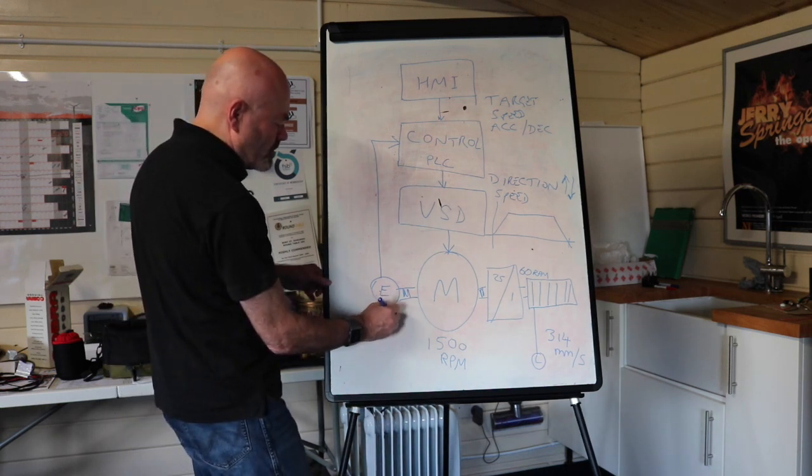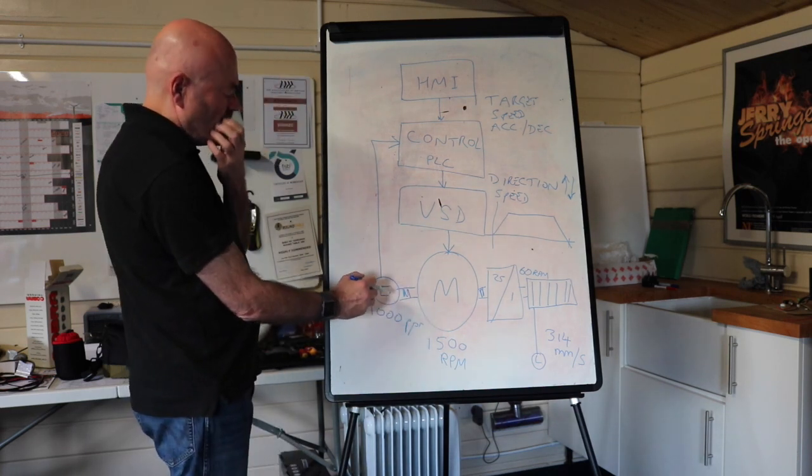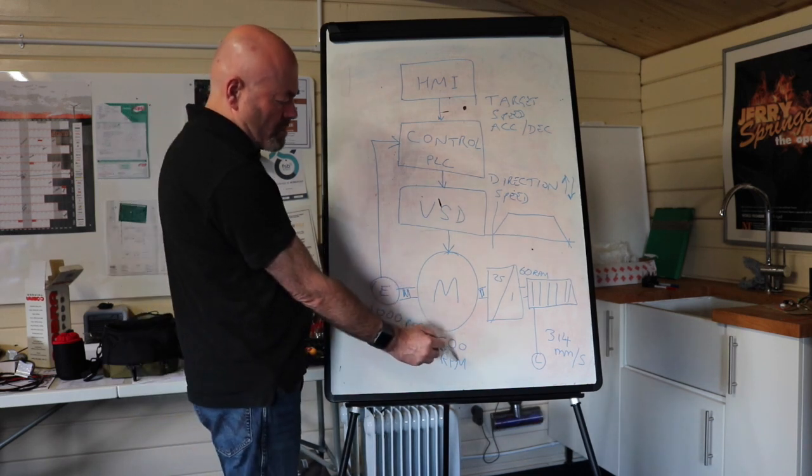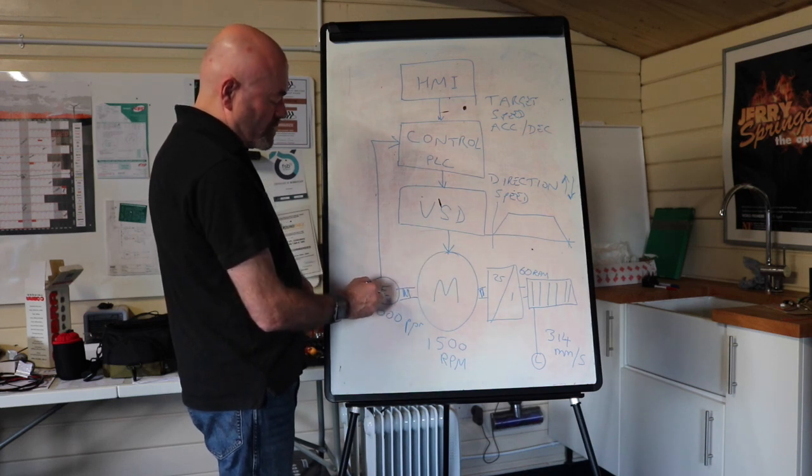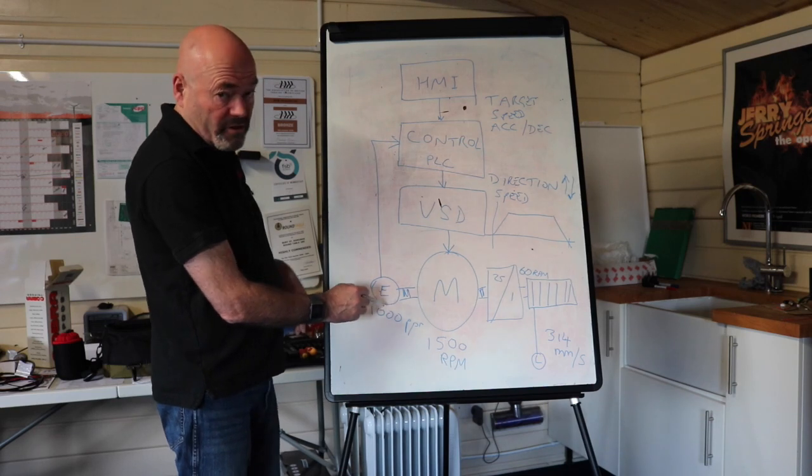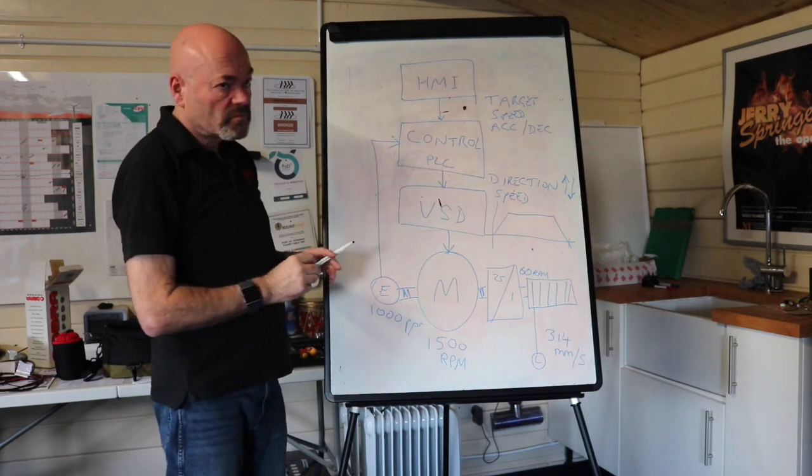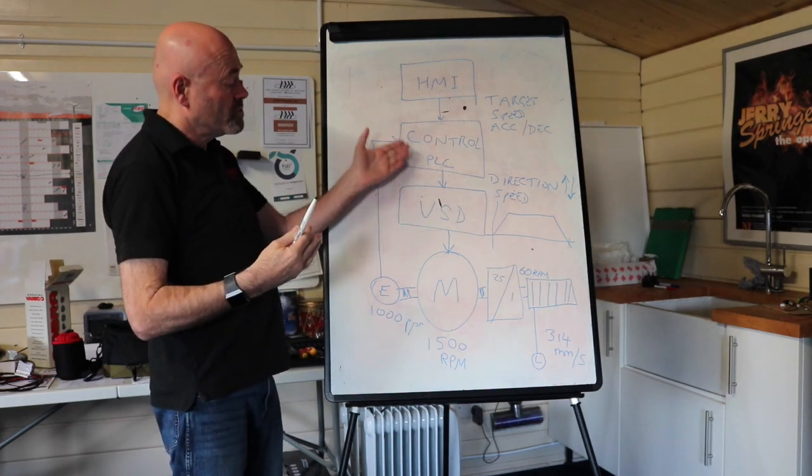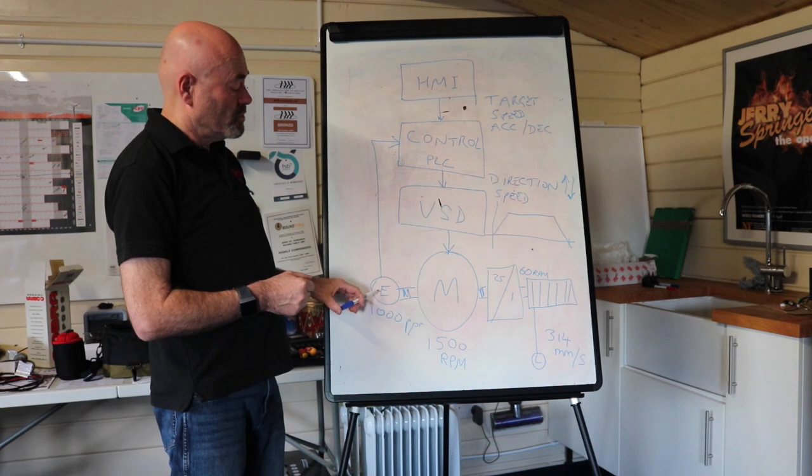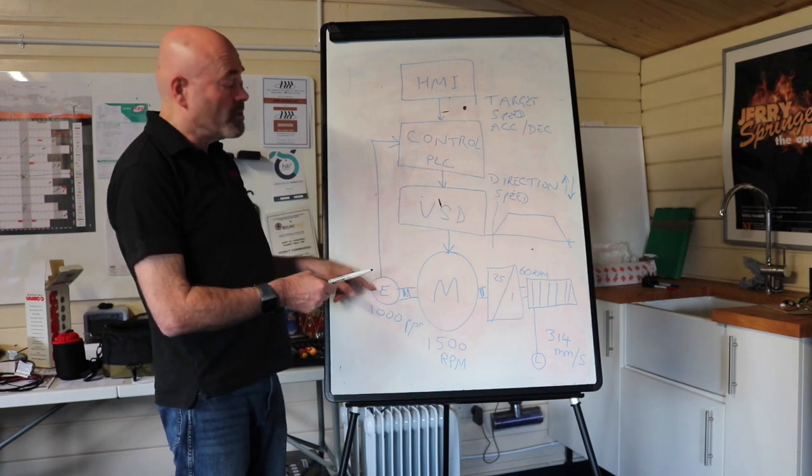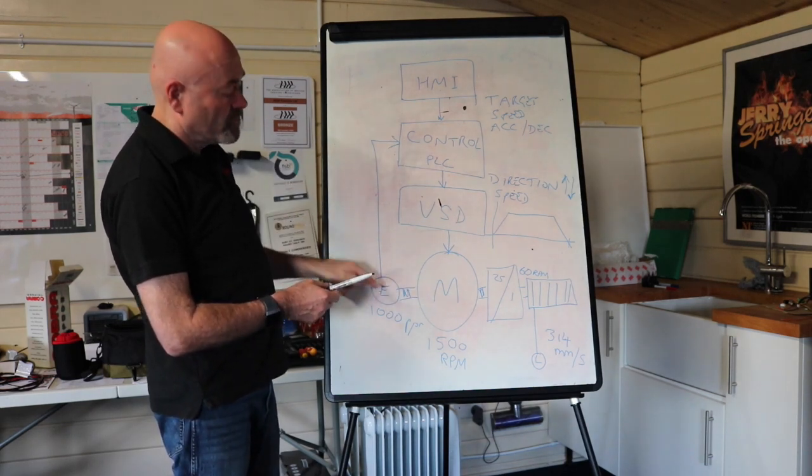So by knowing how many pulses are coming out, it knows how fast the motor is travelling and also can keep up with where the winch is by counting the pulses. So if there were, for instance, a thousand pulses per revolution here, it's a 1500 RPM motor. So this is turning 25 times a second, which means at full speed this encoder is giving 25,000 pulses per second to the control system. So if the control system were asking the motor to go 50%, it's expecting 12,500 pulses back. So by measuring the number of pulses coming back, it knows how fast the system is going. And that is called a closed loop control.